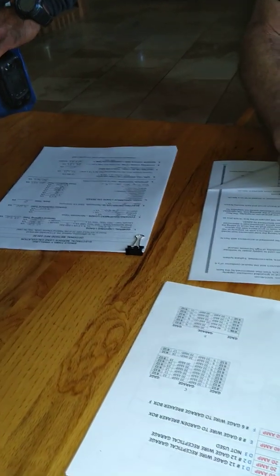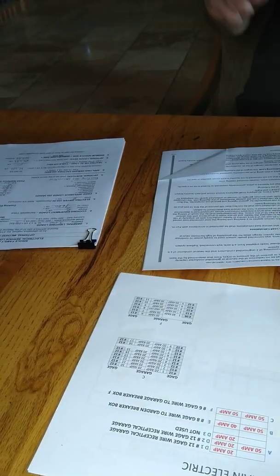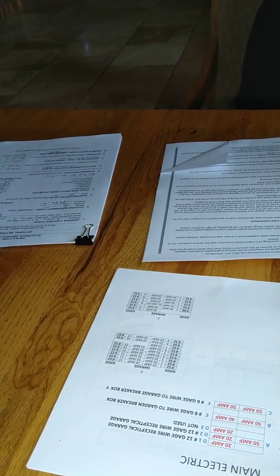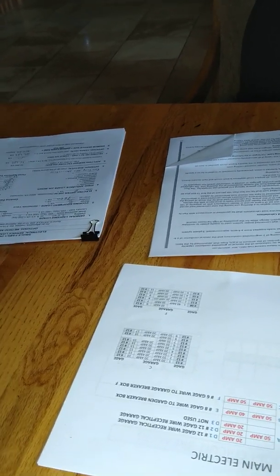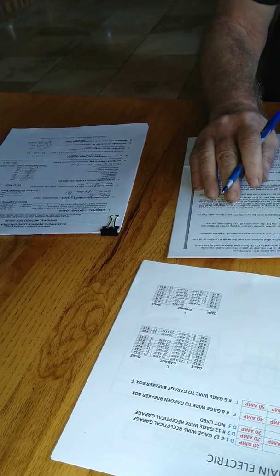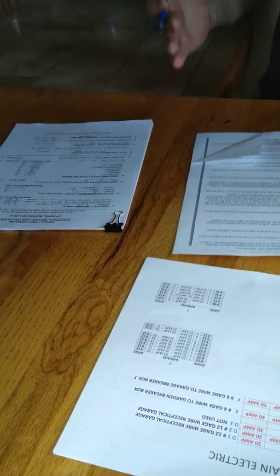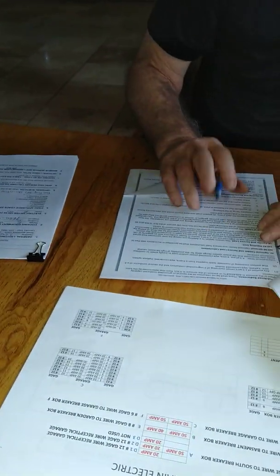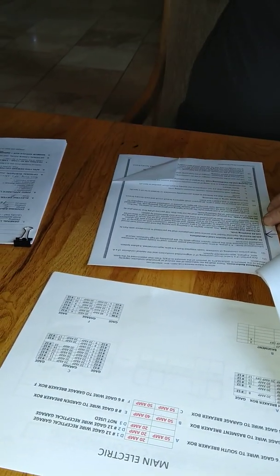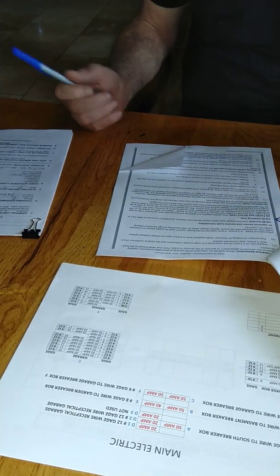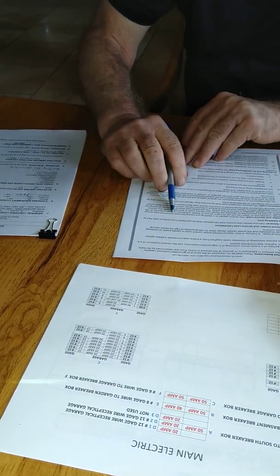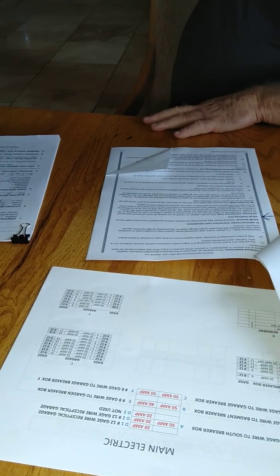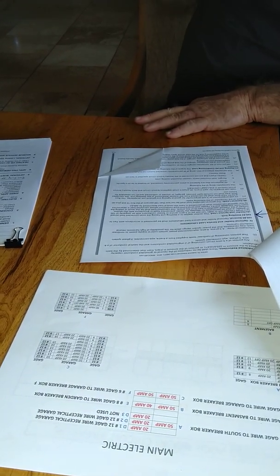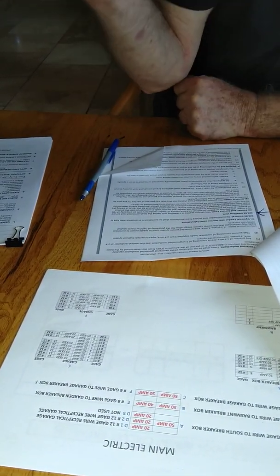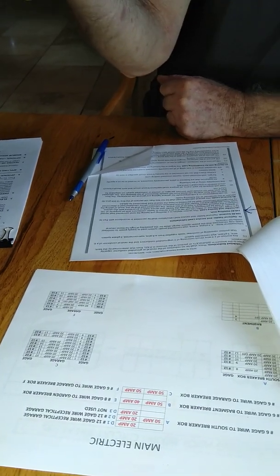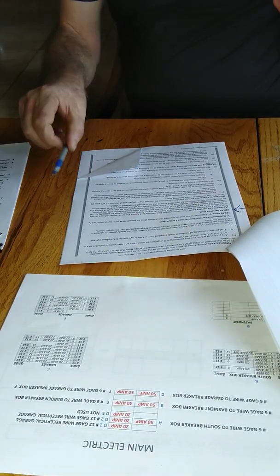Dwelling units, feeder and service loads. What I've done is for each of the bathrooms and the kitchen, I put in a service load or a feeder, what do they call it? Branch circuit of 20 amps. Okay. So that you don't pop your circuit when you're using a hair dryer. So that's all done. Also, throughout the house, we have finished the circuit. All right.